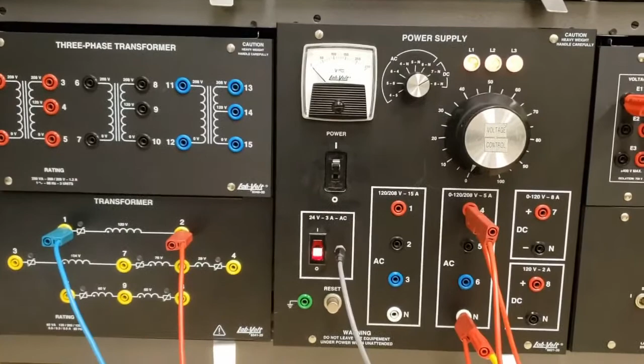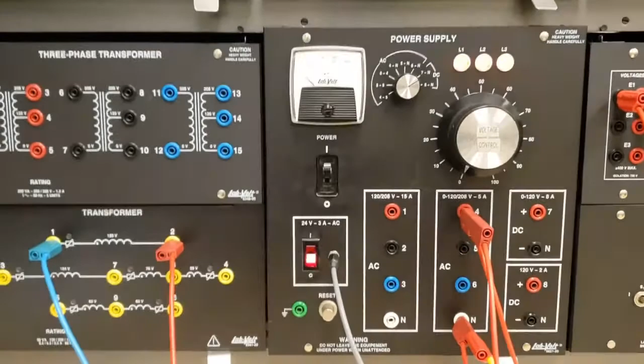So you apply the rated voltage for this test and operate your transformer at its rated conditions, because otherwise the parameters you calculate no longer apply, and you may find performance widely differing. Just be careful of that. The parameters you calculate are purely for that voltage level, and that's why you should apply rated voltage, because that's what your transformer should be working at.